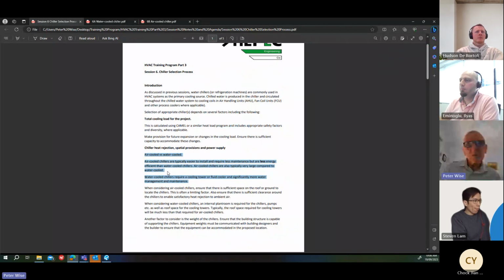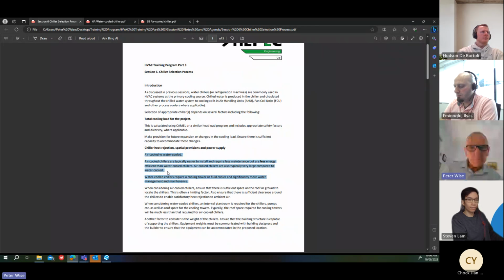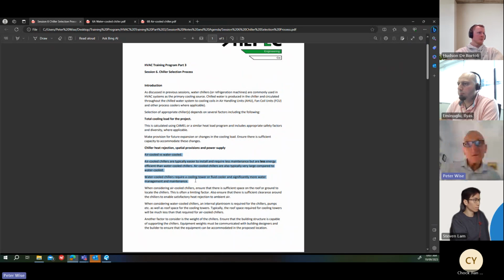A 1,500 kilowatt chiller is roughly 15 metres long, okay? About 2 metres wide, 2.2, and probably about 2.2 to 2.4 metres high. So it's a big piece of kit. A 1,500 kilowatt water-cooled chiller is probably only a few metres long. So that's something to bear in mind. The water-cooled chillers require a cooling tower or a fluid cooler or hybrid cooler, and significantly more water management and maintenance. So there's pros and cons for all these selections.